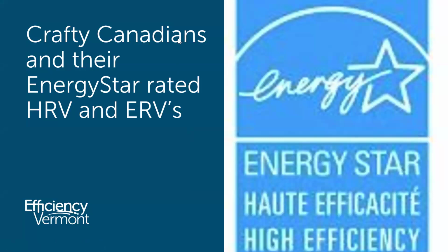We had one from Tom about, does RBES require fresh air supply to all spaces, in bedrooms or common living areas? So it's not calling it out specifically in the code language that a minimum amount of supply is brought to which specific places in the home, but best practice and standard for design is what I've been talking about here to this point: an average of 20 CFM to the bedrooms, the primary bedrooms that'll be lived in, and to the living spaces of the house. And again, in that example we just showed, there's some flexibility within that as you're trying to equalize and balance out your supply and exhaust side.